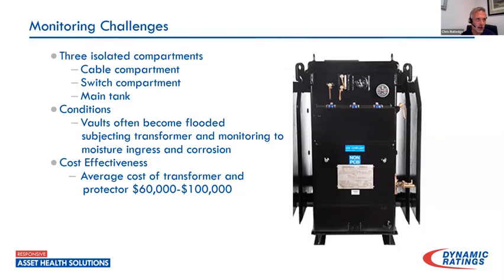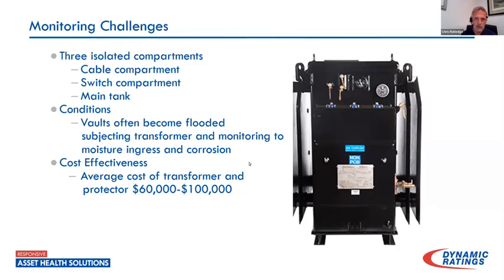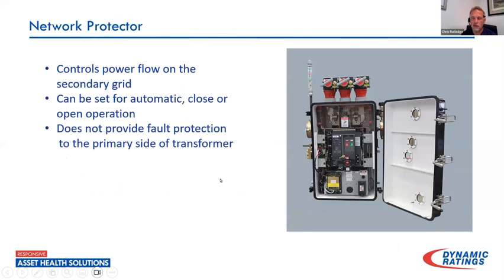Another issue is these vaults flood a lot. In Memphis, being inland, corrosion and flooding wasn't as big an issue, but I've had water lines burst and these things go underwater. They don't have a nitrogen supply system on them. One of the things I had to consider when looking at how to keep these from failing was to understand why they fail — a lot of times due to moisture ingress of some kind, either from degradation of gaskets or degradation of the tank.